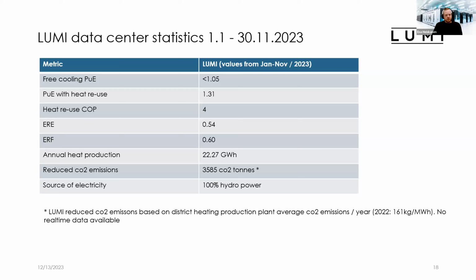And energy reuse factor is so far this year 0.6, so 60% of used energy we have been able to utilize as waste heat. Our annual heat production so far is a little bit over 22 gigawatt hours, and based on this amount of heat production, we have reduced CO2 emissions by approximately over 3,500 tons. This is based on the district heating production plant's average CO2 emissions from last year, which was 161 kilograms per megawatt hour.